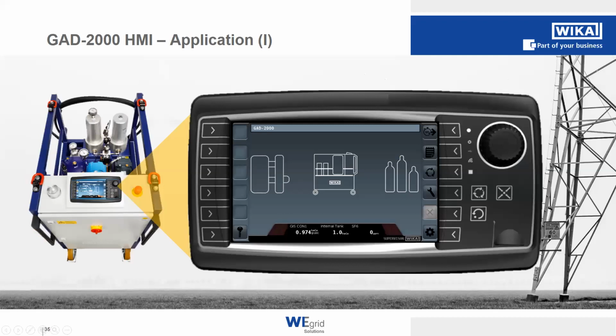How is the GAD operated? We have a fully automatic process structure within our HMI in our control panel. Usually at the home button, it looks like that. We have the gas compartment on the left side. We have our unit in the middle, and also we have the possibility to get new SF6 gas from cylinders or an external source. We also have the pressure level of the gas compartment, and we have a certain pressure level within our GAD.